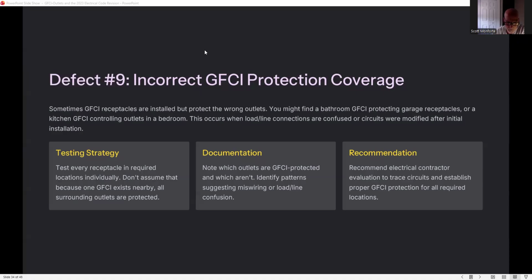Documentation: note which outlets are GFCI protected and which aren't. Identify patterns suggesting miswiring or line and load confusion. Recommendation: recommend an electrical contractor evaluate and trace the circuits to establish proper GFCI protection for all required locations.